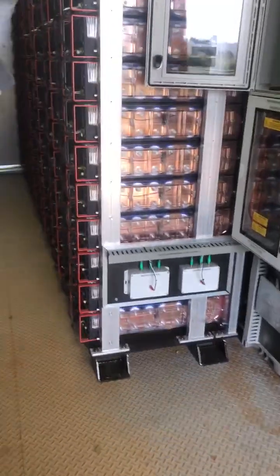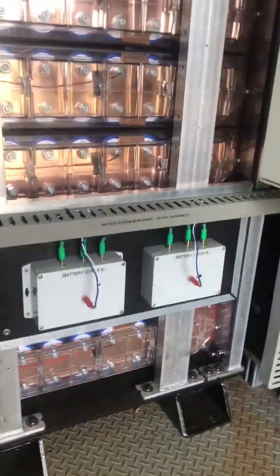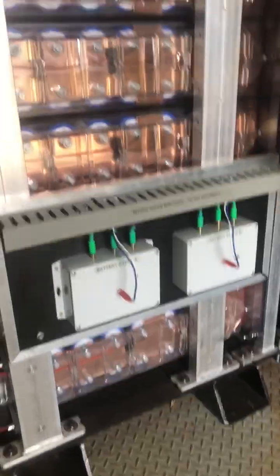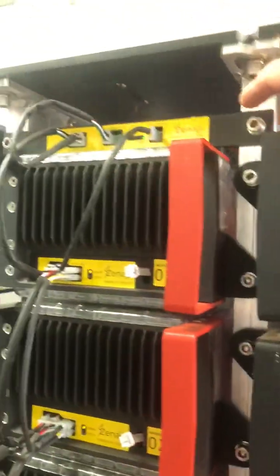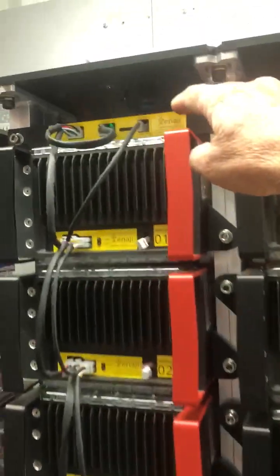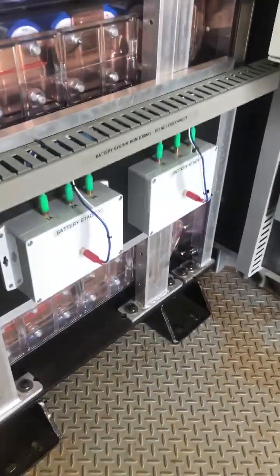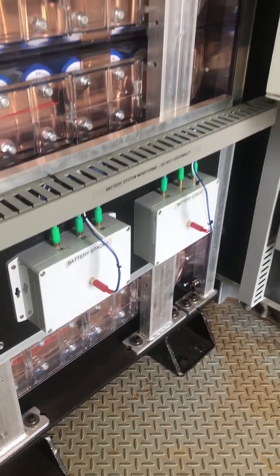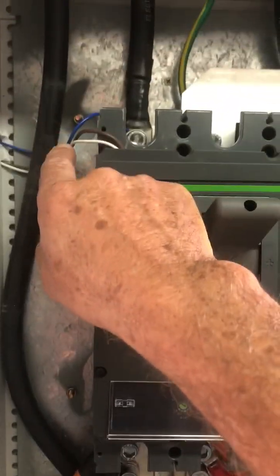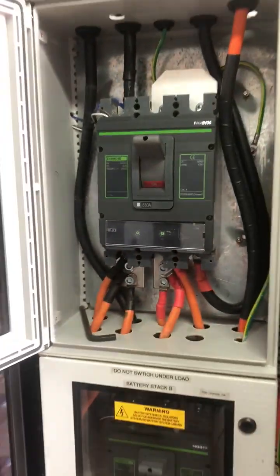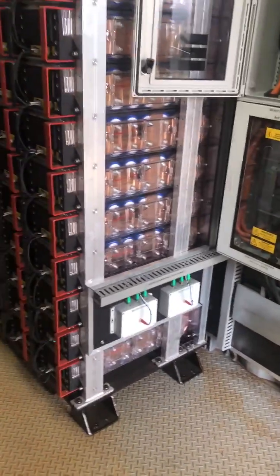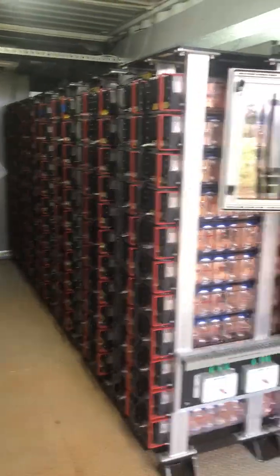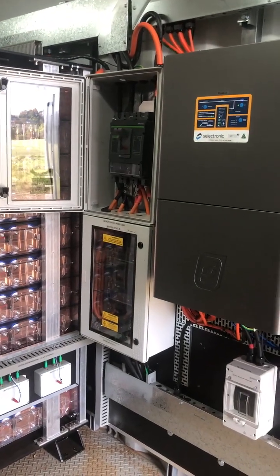Down below, we can see these are what we call the battery controllers. And what these are doing is they're connected to these battery management systems on the top of each stack, like there, and they're all wired back into our collection device here. These two cables here are designed to actually trip the circuit breaker off, so that if there's a fault or some unsatisfactory condition in the batteries, it'll trip the circuit breaker off to provide safety.